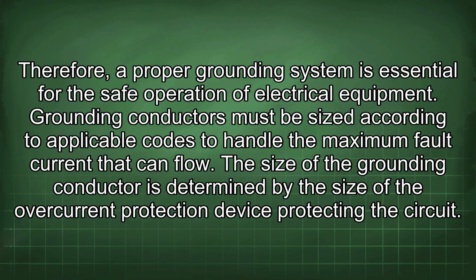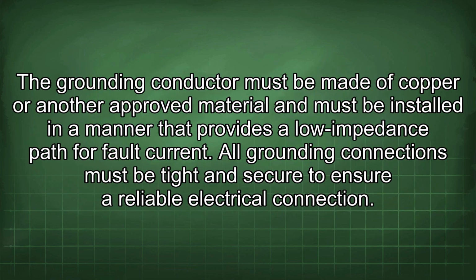Grounding conductors must be sized according to applicable codes to handle the maximum fault current that can flow. The size of the grounding conductor is determined by the size of the overcurrent protection device protecting the circuit. The grounding conductor must be made of copper or another approved material and must be installed in a manner that provides a low impedance path for fault current.